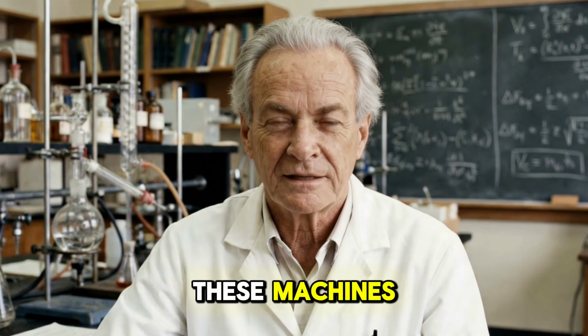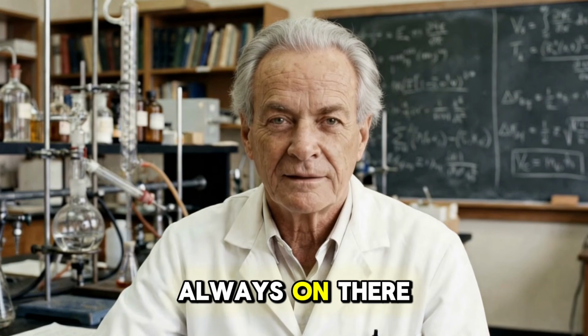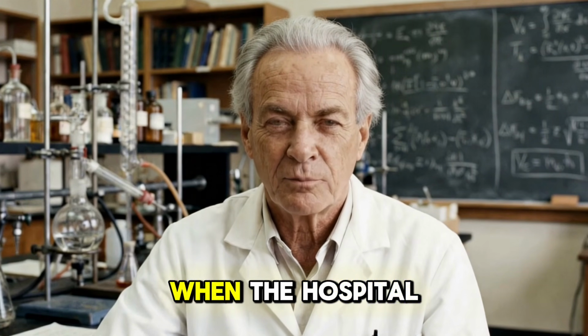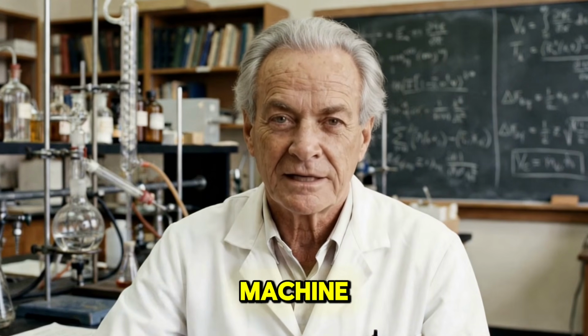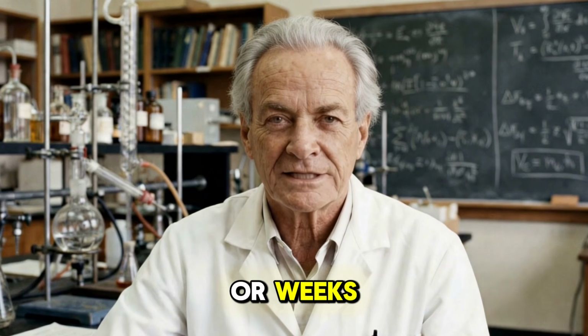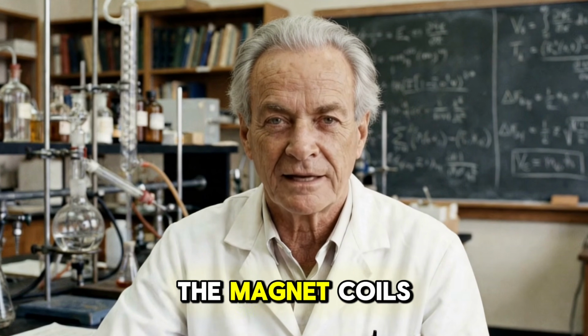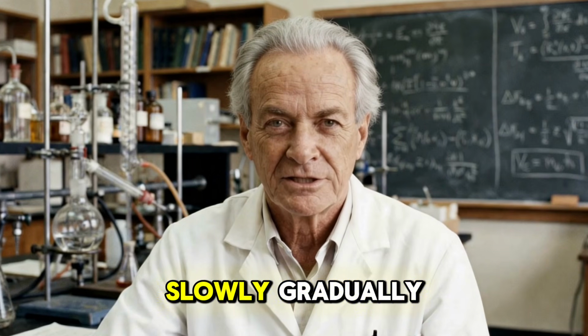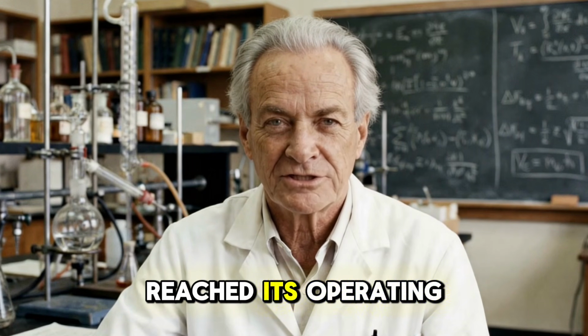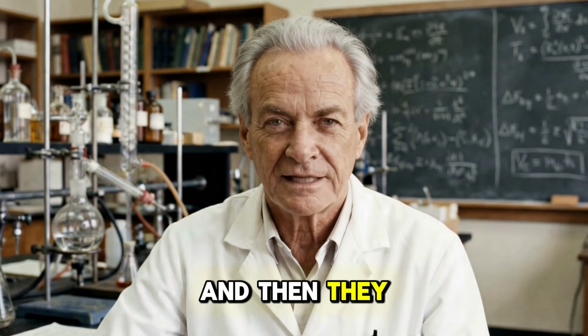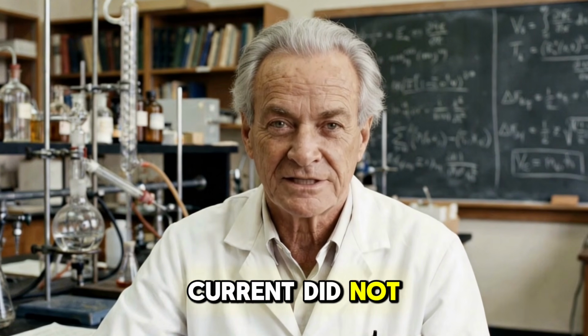That field is always on. There is no switch. When the hospital installed that MRI machine, technicians spent days or weeks carefully ramping up the current in the magnet coils. They raised it slowly, gradually, until the field reached its operating strength. And then they stopped. But the current did not stop.